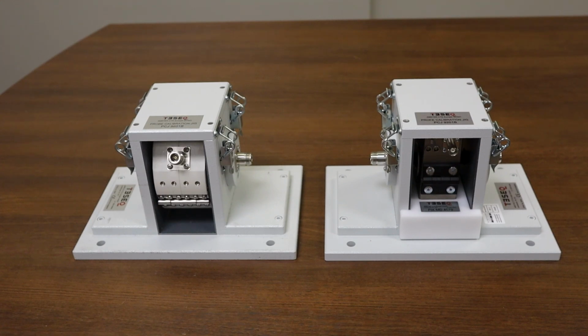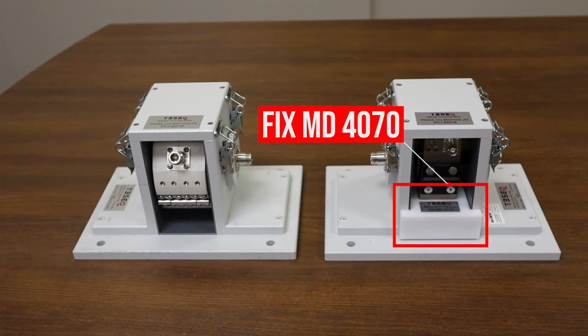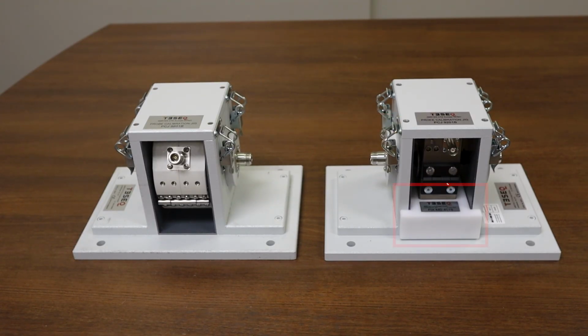Taking a look on the right at our MD 4070A, we have the Fixtures MD 4070 underneath the monitoring probe, which is mounted upside down inside the PCJ 9201B calibration fixture. As we mentioned previously, the Teseq injection probe and monitoring probe lend themselves well to a variety of conducted RF immunity requirements given the frequency ranges of 4 kHz to 400 MHz.